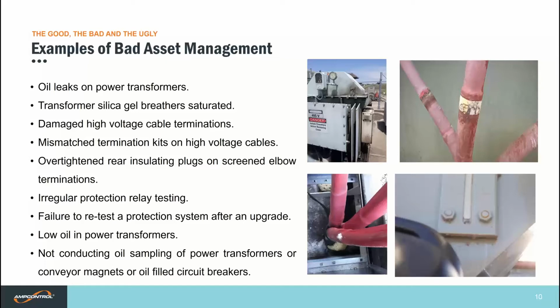With as-found high voltage cables, or upgrades and replacement of high voltage switchboards, cable testing first can give you a footprint of that cable under test. It can then be documented, and the deterioration in that power system can be flagged. In buried services scanning, a customer may be looking at extending a switch room or a switch yard and needs to know what's in the ground. Thermal cameras have come a long way, and a simple drive-by of your private overhead network can pick up loose connections, burnt contacts, and tracking on wooden cross arms. When carrying out all of these services, the resultant condition report can then offer recommended maintenance or replacement of suspect or end-of-life equipment.